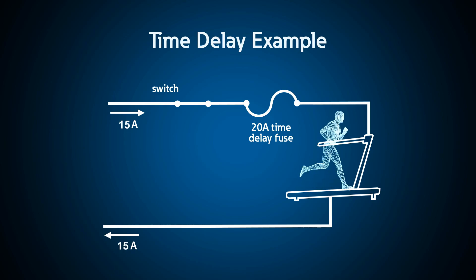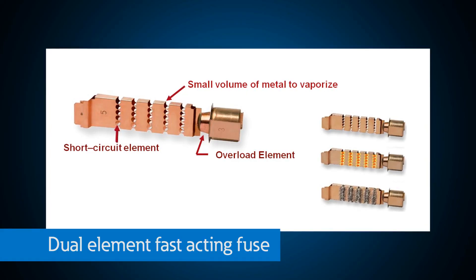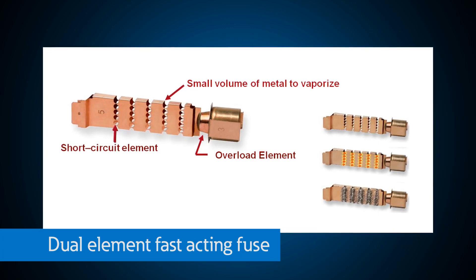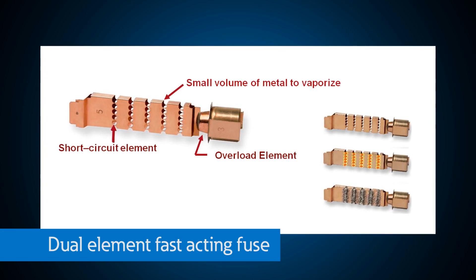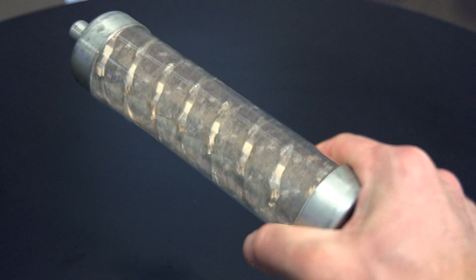That pin-like mechanism provides overload protection — lower persistent overcurrents must persist long enough to melt that portion of the element. If the current appears and then disappears, the fuse does not open; it only opens on persistent current. The other key area is a series of holes and pinch points — resembling little-baby swiss cheese. This element carries current, and on very high fault currents these pinch points basically erupt. The entire cavity is filled with sand; when the pinch points see very high fault current, the surrounding sand turns to glass — an excellent insulator — limiting those high fault currents and protecting equipment.